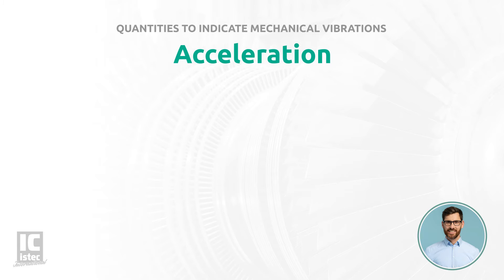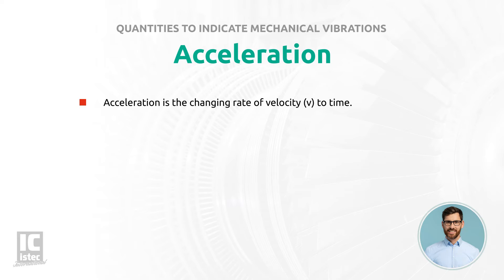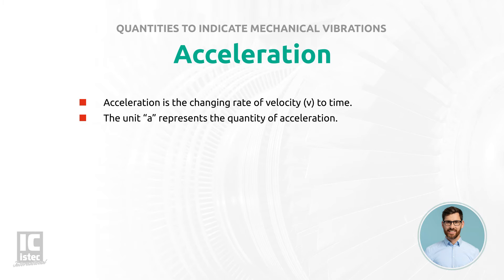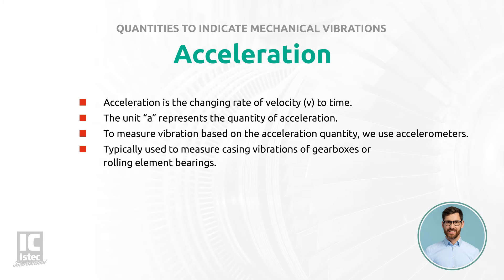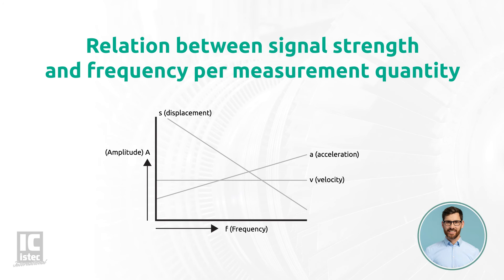If we take a look at this plot, we can conclude that the acceleration is the changing rate of velocity to time. The unit A represents the quantity of acceleration. To measure vibration based on the acceleration quantity, we use accelerometers. These sensors are typically used to measure casing vibrations of gearboxes or rolling element bearings. If we take a look at this plot, we can conclude that the relation between the signal strength and frequency determines which sensor is best to be used for a specific application.